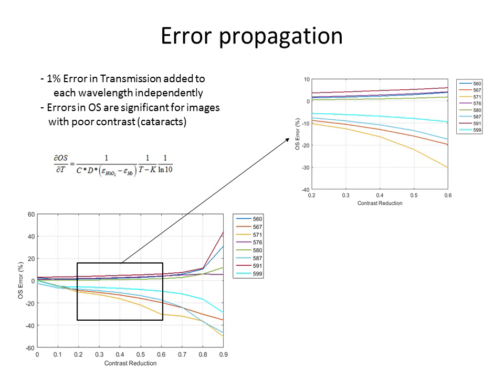You wouldn't have this if you use the model without the contrast reduction. This is basically because of this factor here. This is the sensitivity of oxygen saturation to errors in transmission. If you don't have this factor, that you wouldn't have in a regular Beer-Lambert law, you will still have error propagation, but it won't be too big of a problem. But once you introduce the contrast reduction, when K increases, this will be small, so this will be big. It will escalate quite a lot there.